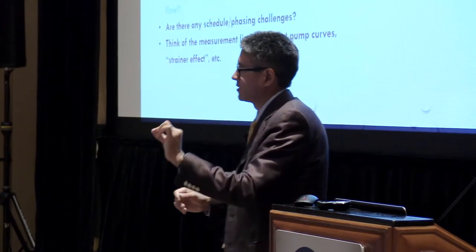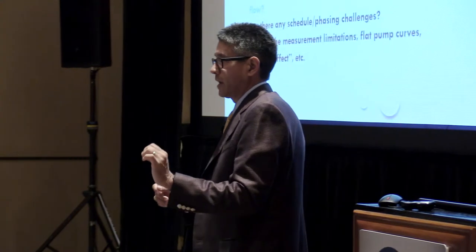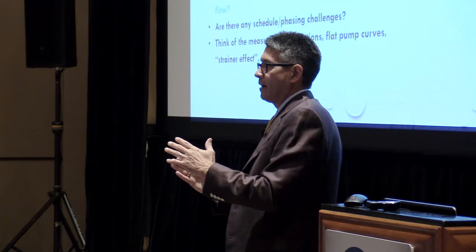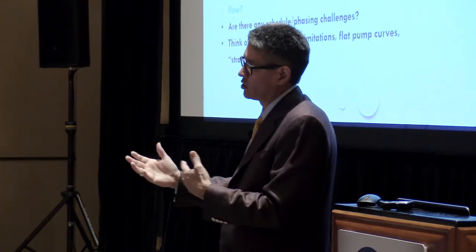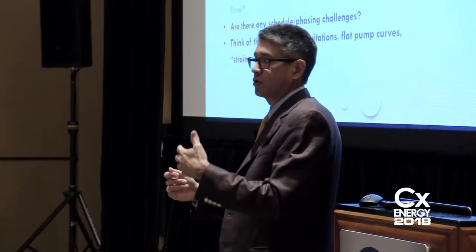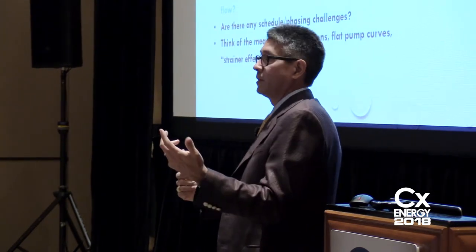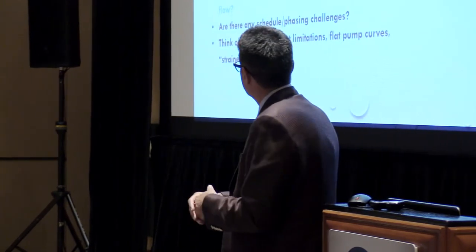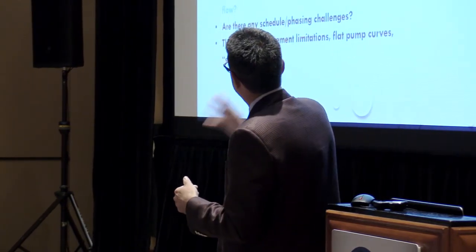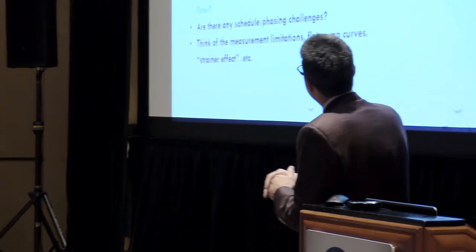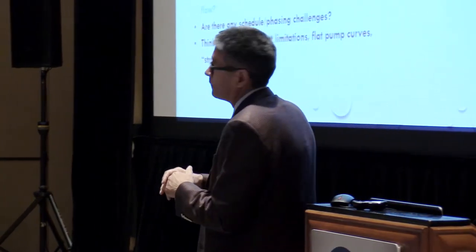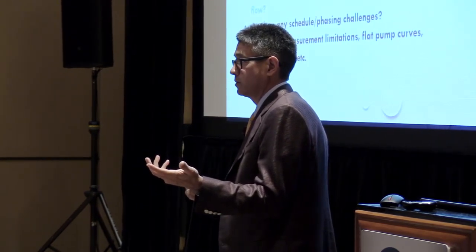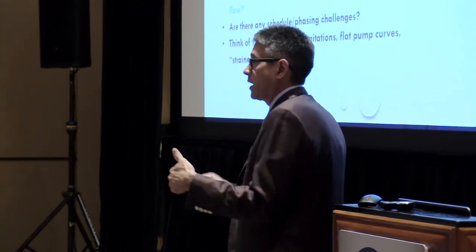It's amazing that they all of a sudden see how little water flow that is and how much you're trying to regulate. And you start thinking, hey, does that really matter if I have 1 GPM of overflow on a half a GPM? Maybe, maybe not. If you start thinking we do have an overflow issue, then maybe you should be looking at using automatic flow limiting devices and then prevent an overflow issue in that scenario. Because the one thing you always, that ASHRAE had a study back, 90% of heat transfer is obtained at 50% of water flow at the 180 degree water temp. So you still get your BTUs, even though your flow is down on that side at 90%.